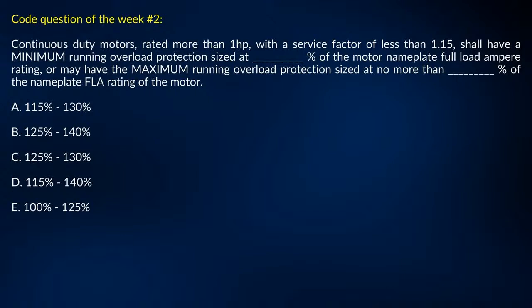Okay, so that would fall under other motors, and you would look at 430.32A1 for the minimum, and then you're going to look at 430.32C, and that would pick up for your maximum. And since you don't have a temperature rise there, that would be 115 and 130%. I go with A.